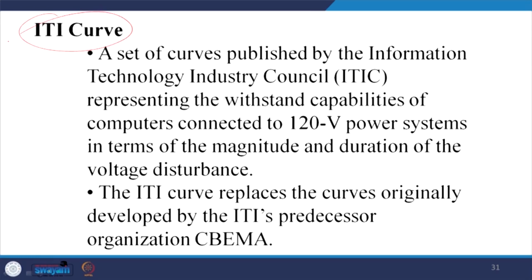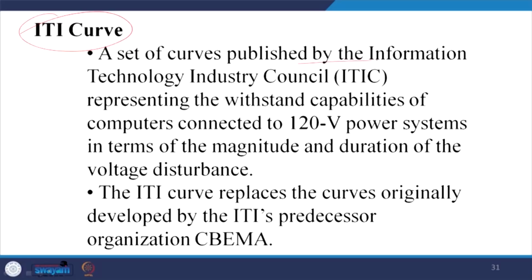Thereafter this CBEMA curve has been modified a little. Now computer manufacturers all over the world follow this ITI curve. It is a set of curves published by the Information Technology Industry Council, ITIC. They just changed the name from computer to information technology industry.